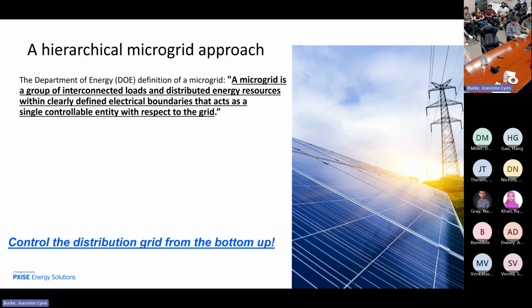This is a quick definition of a microgrid from the DOE. The key words here are single controllable entity. That means any point in the grid where I have the ability at a single point to control the flow. They call it a POI, a point of interconnection to the grid where I control the flow, and that doesn't have to be a residence or a commercial building. It can be any point in the grid where all the power will flow through that point with no other uncontrollable sources.